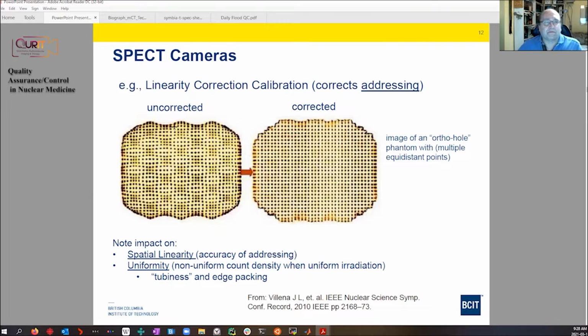And you can see a couple of gross issues with it. Notice the dots are closer together here. That would result in a higher count density in this region. This region corresponds to over the center of the PMTs. Notice here, between them, you've got them spaced out further. That would result in a lower count density. And so if I could ask everybody to squint a little bit, you would see that this produces a pattern where you see these circles of hotter and colder counts.